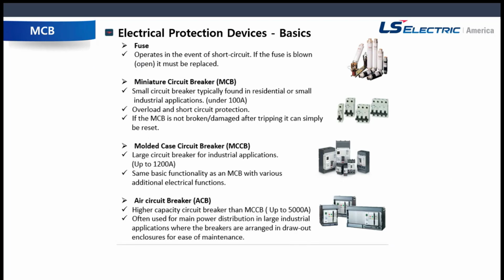So let's go over some basics of electrical protection devices. The fuse will go off in the event of a short circuit. If the fuse is blown, it has to be replaced. Miniature circuit breakers are typically found in residential or small industrial applications, typically under 100 amp, and they provide overload and short circuit protection. If the MCB is not broken or damaged after tripping, you can just reset it. It's very easy and typically works much better than a fuse depending on your use case.